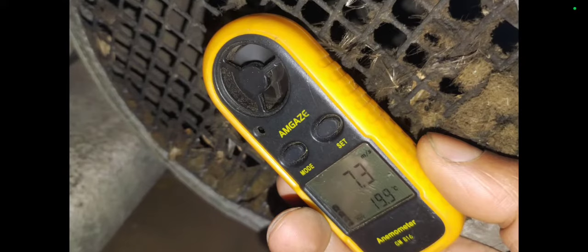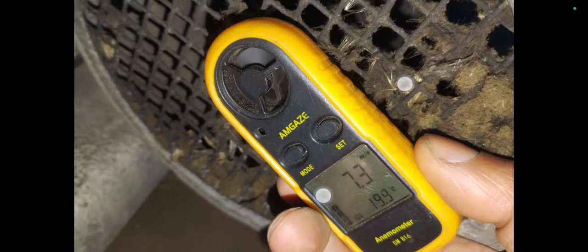Okay, and this is another plant room. So before cleaning this, I gave it a check to see the supply fans' meters per second of air coming into the room. And then here I am changing the probes, so the ignition I'm changing and the detection on this particular boiler. This was another boiler where it hadn't been shut off properly. I'm starting to get frustrated with this. I'm going to boilers after someone and I'm not getting any sign whether the boiler's been commissioned or not. So make sure you carry out your checks when you come across boilers.